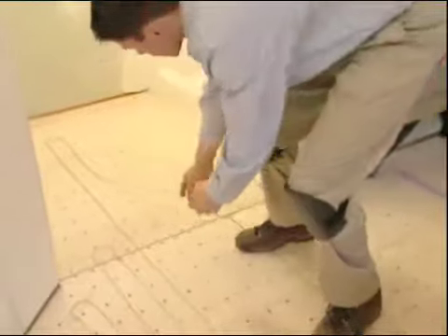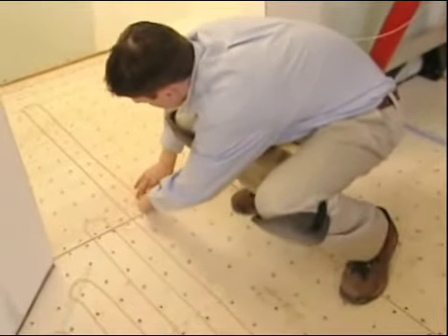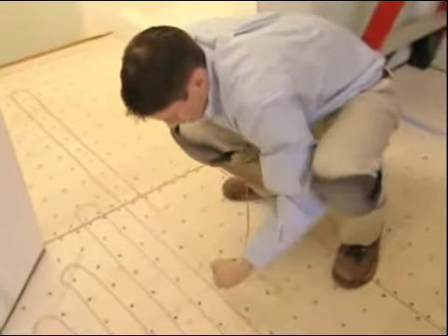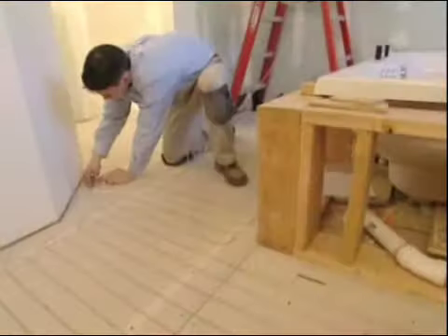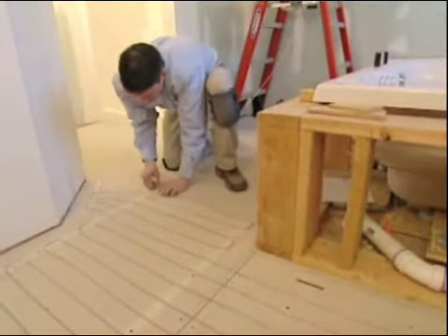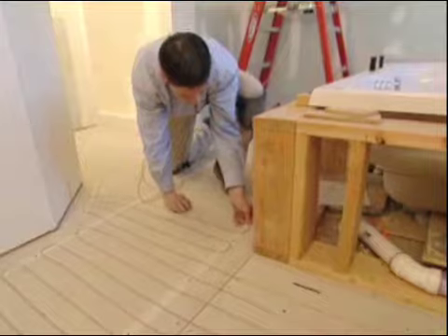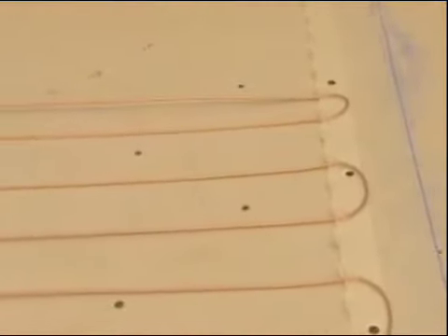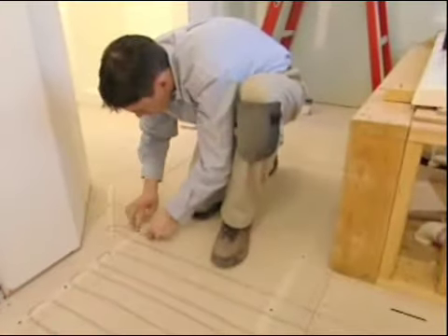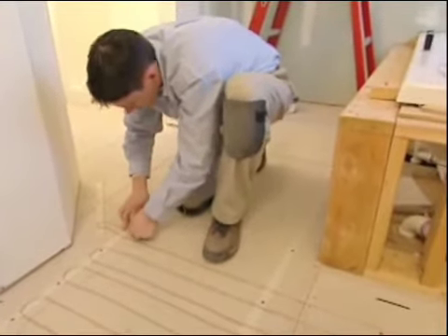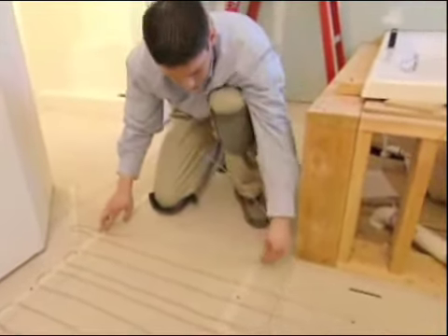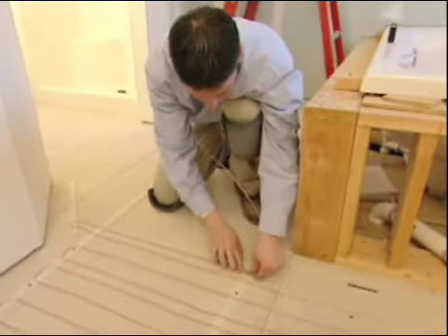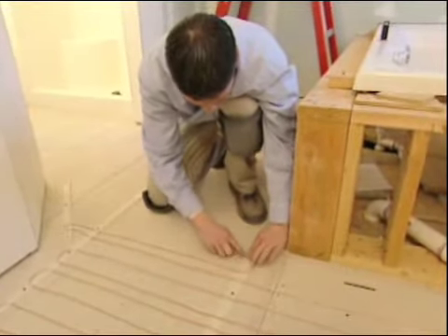If the label has not reached the location marked on the floor, leave the low traffic area unheated. If the label has passed the mark, carefully lift the previous few cable runs and place in a 1.5 inch spaced run between the 3-inch runs to use up the excess cable. No less than 3 standard intervals of cable spacing should separate these additional 1.5 inch intervals.